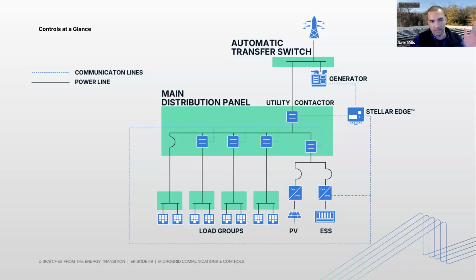If we zoom out a little bit, like rewind to how did we even come up with this architecture in the first place? The place that we start when we are meeting with a client and doing our design meetings and trying to figure out what the right system for them is, is to really figure out what you're trying to do, right? Which loads do you intend to support? Because some of these might be HVAC loads, which may or may not be important for that site. Some of them may be EV chargers, which we would almost certainly cut out during an outage. And some of them may be critical loads, in which case we wouldn't even cut them out. And that's like the one on the far left where we don't even put a load shedding contactor on it because we always want that to be powered.